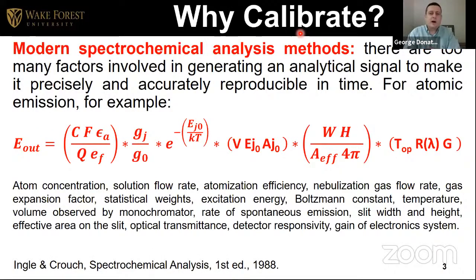So first, why would anybody need to calibrate an instrument to do quantitative measurements? In modern spectrochemical analysis methods, there are too many factors involved in generating the analytical signal. If you look at this equation, you can see the factors, and here is what they mean. You have atomic concentration, solution flow rate, and so forth. So it's very hard to control all this and reproduce it in time. If you run a calibration curve now and come back tomorrow, the signal is not going to be exactly the same because of all those factors that will change from now to the next time.